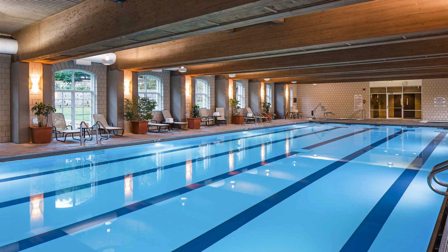An important aspect of indoor pool HVAC systems is energy efficiency. Due to the constant operation required to maintain comfort and prevent moisture problems, these systems can consume significant amounts of energy. Here are some ways to improve efficiency. Heat recovery ventilators, HRVs. These systems capture heat from exhaust air and transfer it to incoming fresh air, reducing the energy needed for heating. Variable speed drives, VSDs, allowing fans and pumps to operate at variable speeds, can significantly reduce energy consumption. Energy-efficient components. Choosing equipment with high efficiency ratings can substantially lower operating costs.